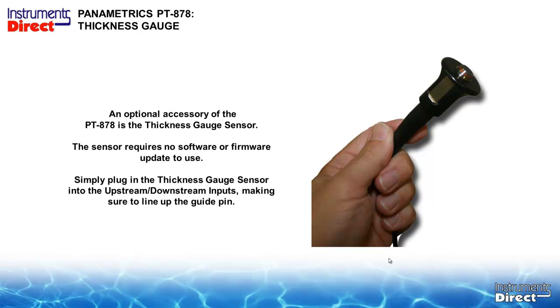There's an optional thickness gauge you can get for the PT878. In all honesty, it's overkill in many cases because the ANSI pipe chart book is usually quite sufficient. The thickness gauge itself will measure continuously from the outside of the pipe to the inside of the pipe. It will not pick up anything that's non-metallic. So if you have calcium buildup on the inside of the pipe, or gel on the inside of the pipe, it's not going to see that.